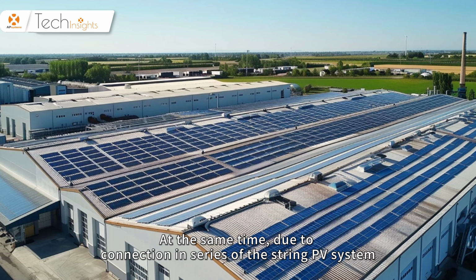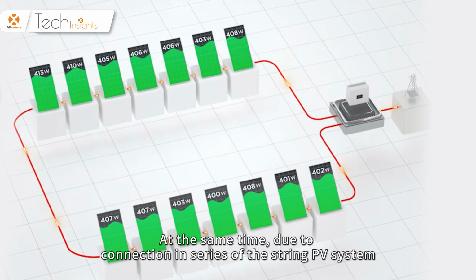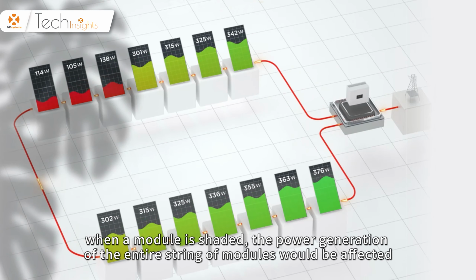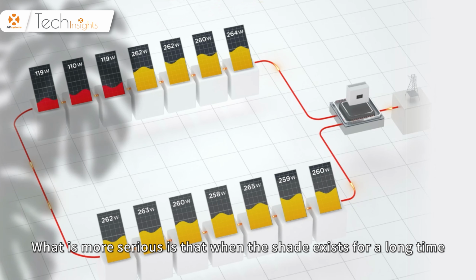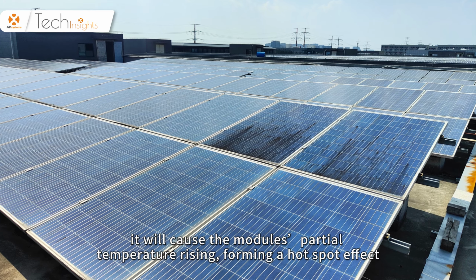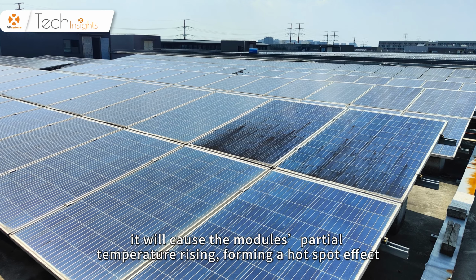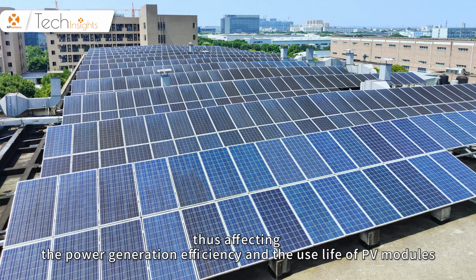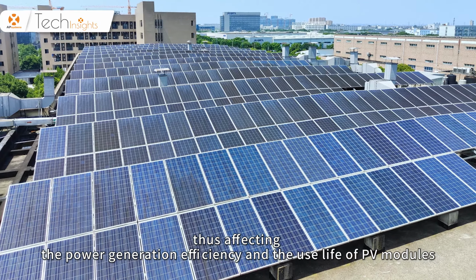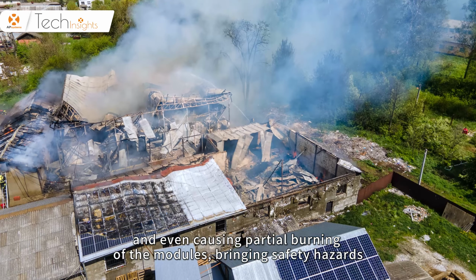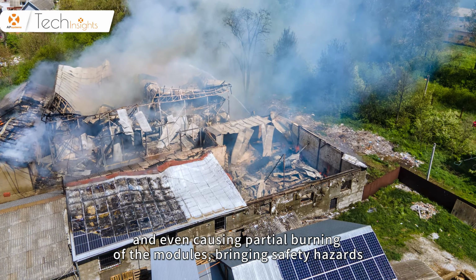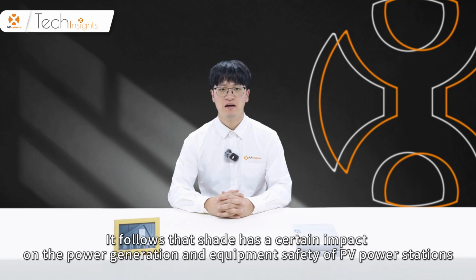At the same time, due to connection in series of the string PV system, when a module is shaded, the power generation of the entire string of modules would be affected. What is more serious is that when the shade exists for a long time, it will cause the module's partial temperature rising, forming a hotspot effect, thus affecting the power generation efficiency and the use life of PV modules, and even causing partial burning of the modules, bringing safety hazards. It follows that shade has a certain impact on the power generation and equipment safety of PV power stations.